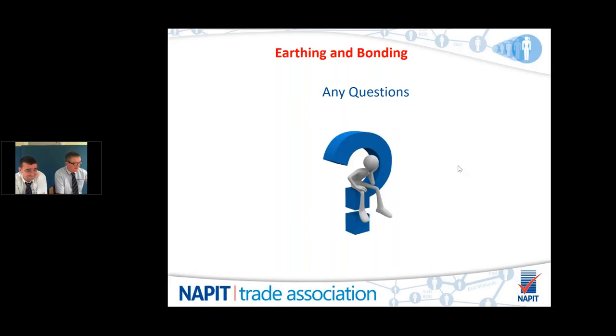Adequate. Yeah. I'm sorry, but I'll have to use adequate. And I do apologise, but I'm just going to look at the regulations. It's 134, I believe. No, it's not. I knew it was not. It's 132.16. And when it states in the regulations, additions and alterations, it is no addition or alteration, temporary or permanent, shall be made to an existing installation unless it has been ascertained and the condition of any existing equipment, including that of the distributor, will be adequate for the altered circumstances. Then it goes on to say, furthermore, the earthing and bonding arrangements shall be adequate.